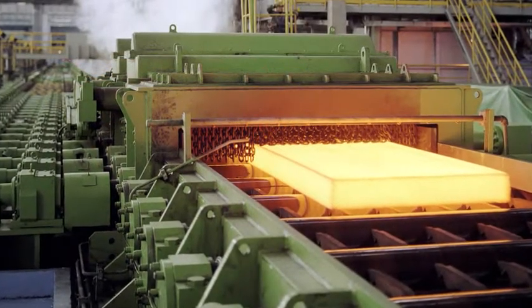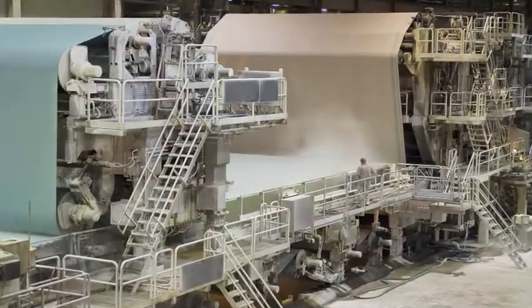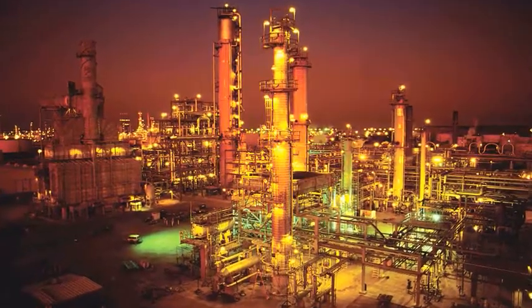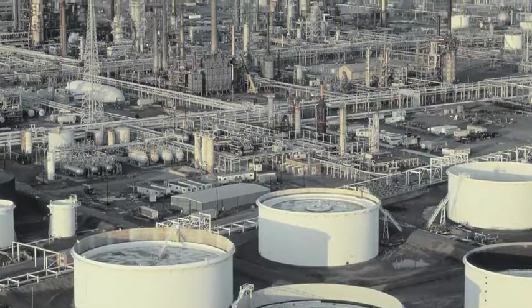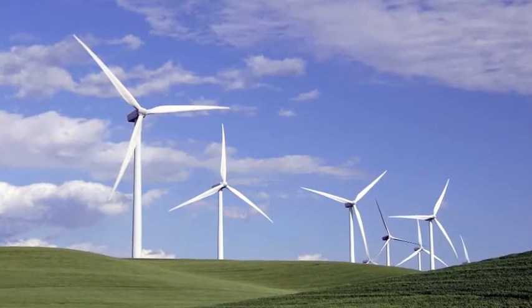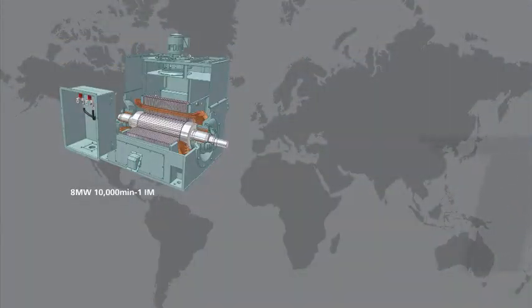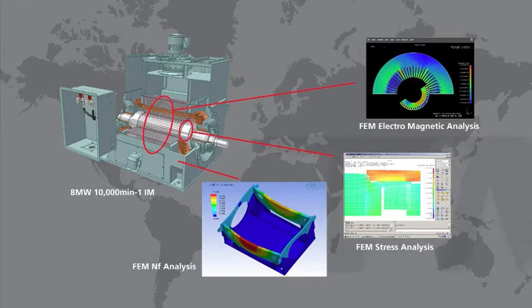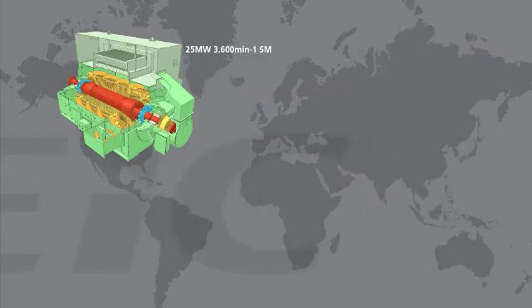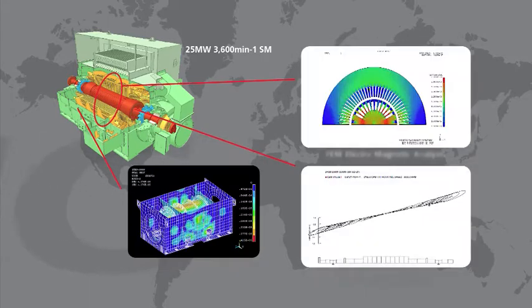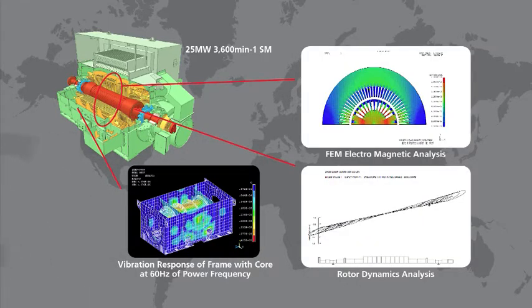TMEIC's worldwide experience includes motors for metal rolling mills, paper plants, petrochemical plants, electro-power plants, nuclear power plants, water and waste plants, mining machinery, and wind generators. Motor designs are improved through extensive use of enhanced computerized finite element analysis to predict such things as electromagnetic field strength, rotor mechanical stress, and frame natural frequencies. This is an example of analyzing an 8 megawatt high-speed induction motor running at 10,000 RPM. In this analysis, a 25 megawatt synchronous motor running at 3,600 RPM is analyzed for frame vibration, critical rotor speed, electromagnetic field strength, and operation at high RPMs.